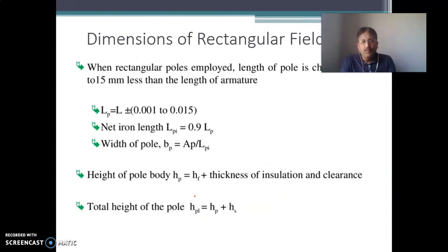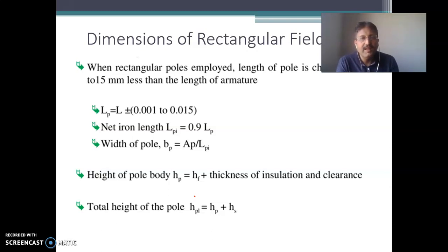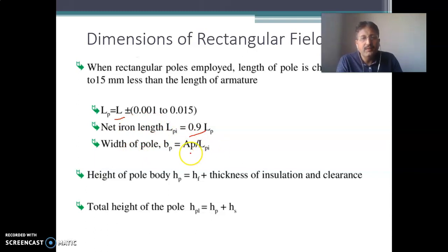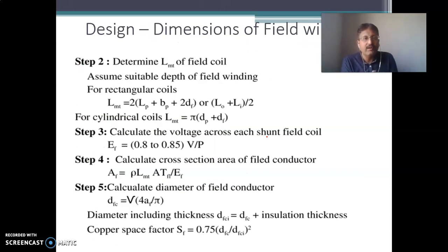If the field pole is rectangular, you have to choose the length of the pole — the length of the pole is generally 10 to 15 mm less than the length of the armature L. Once you get the length of the pole, consider the net iron length by applying the stacking factor of 0.9. Width of the pole is the area of the pole divided by the net iron length. The height of the pole body is height of the field winding plus thickness of insulation and clearance.